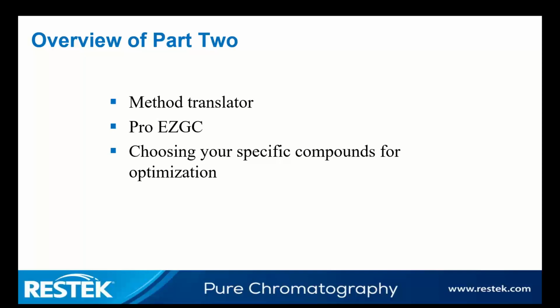Now, the key to doing a translation to another carrier gas when you're using mass spec is to decrease the flows. You really want 0.5 milliliters per minute or less if you are using hydrogen or another carrier gas other than helium. And the idea behind that is we don't want to increase the source pressure on the mass spectrometer, because therefore we're going to lose sensitivity and have a lot of noise in the background from the electron multiplier.